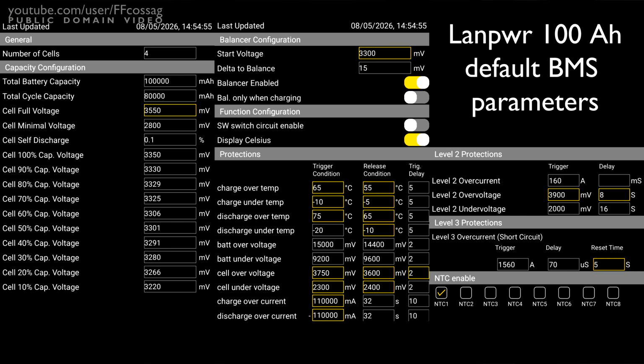It's perfectly adequate. So thankfully the BMS in this battery is a JBD, which works with the Overkill Solar app, which enables you to both read and edit the parameters of the battery. And that's really important because sadly they have not configured this battery very well at all. Most importantly, the protections are not good. We have a charge over temp of 65 degrees, which is too high, a charge under temp of -10 degrees, which is too low, and a discharge over temp of 75 degrees, which is just insanely high. These temperatures should be in the 50-ish degree range, in my opinion, and the charge under temp should be closer to 0 degrees.